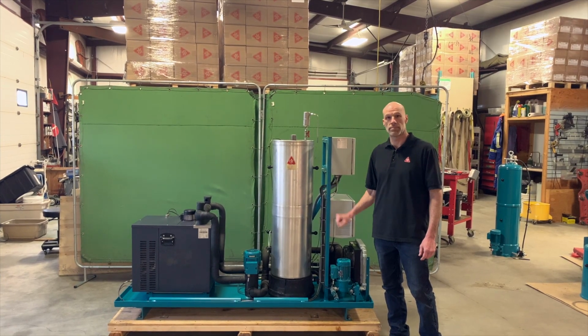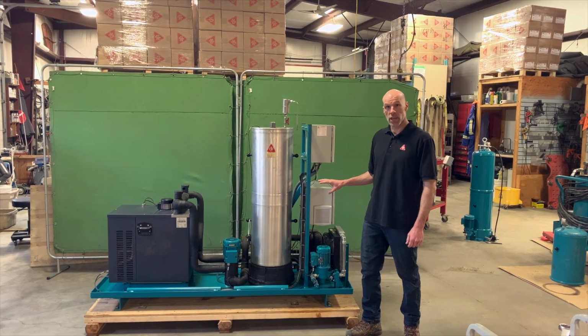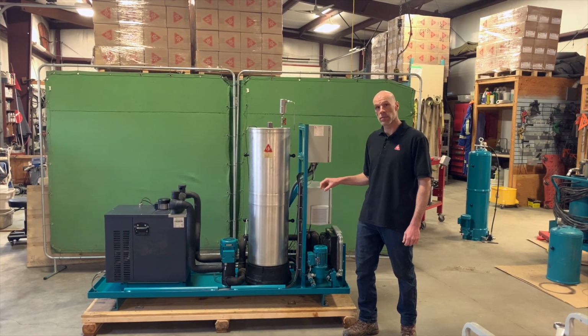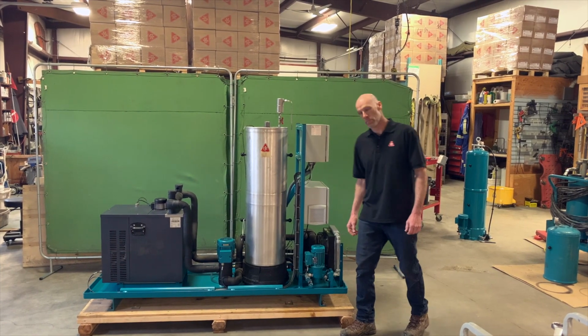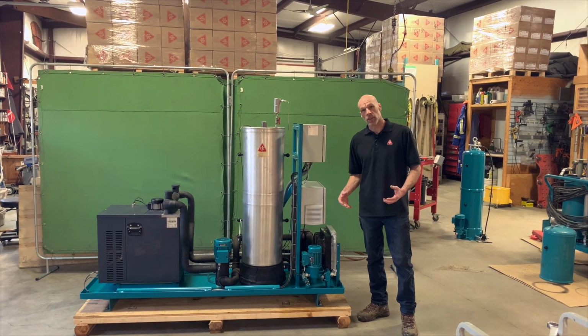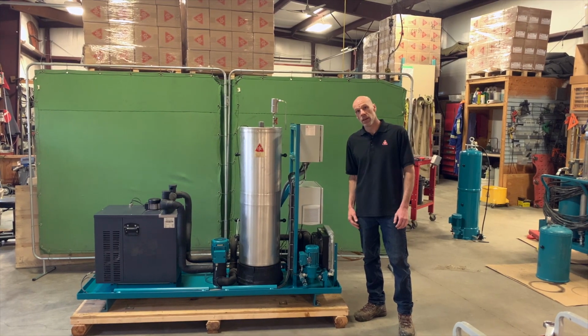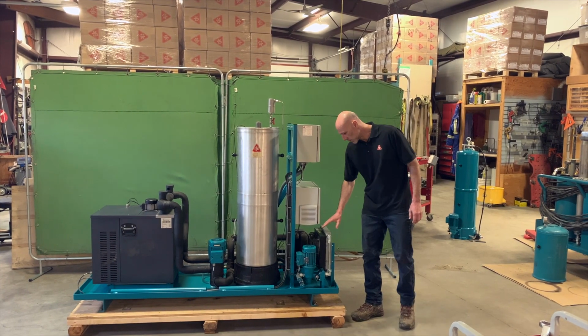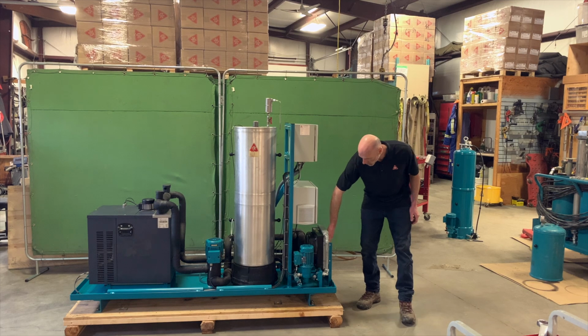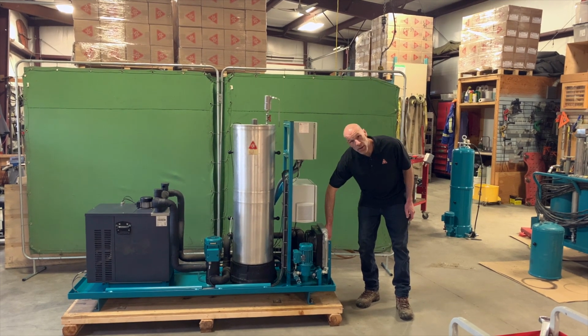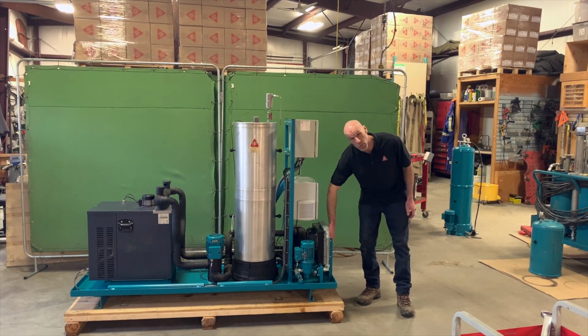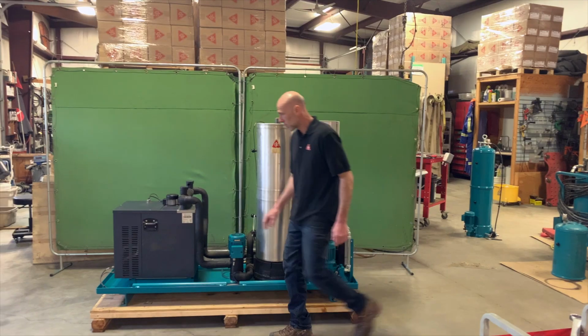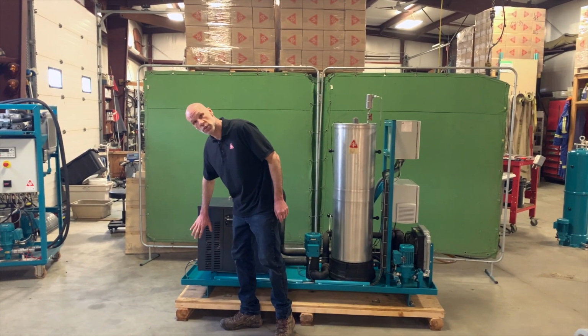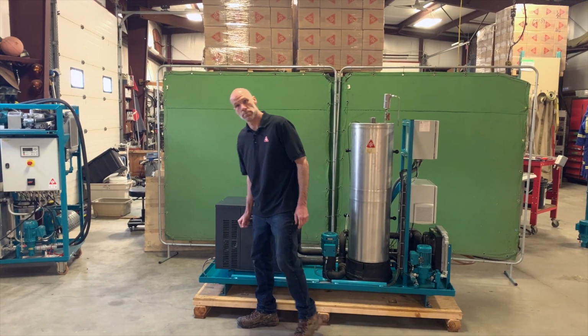There's a few things that you'll want to check and do while the unit is running to make sure you have reliable operation. If you're running in a dusty environment such as a pulp mill, often the fibers will cling to things like the radiators, so make sure that you clean this out either with compressed air or with low pressure water. And also there are some fins in the chiller assembly that you'll need to clean as well.